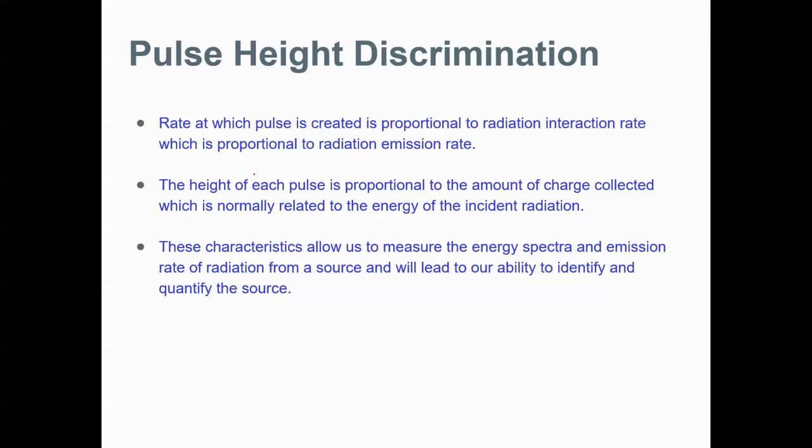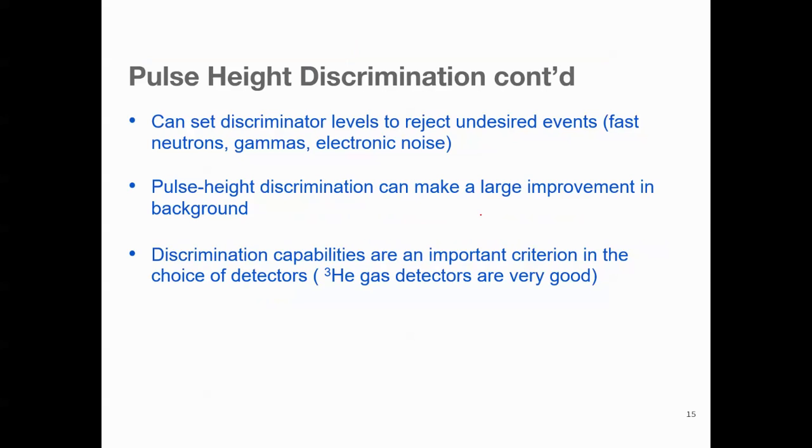To tackle this, pulse height discrimination is applied. The idea behind pulse height discrimination is that the pulse we get from the electronic system of the detectors, we can analyze it, and we know that the rate at which the pulse is created is proportional to the radiation interaction rate, that is the rate at which the radiation is interacting with the detection system, which is proportional to the radiation emission rate, and the height of each pulse is proportional to the amount of charge collected, which is related to the energy of the incident radiation. These characteristics will allow us to know the radiation emission rate and the energy of the incident radiation and will help us to identify and quantify the source. Technically, we can do this by setting discriminatory levels to reject the undesired events like fast neutrons, gamma, and electronic noise. Pulse height discrimination can make a large improvement in background. Discrimination capabilities differ for different choice of detectors.